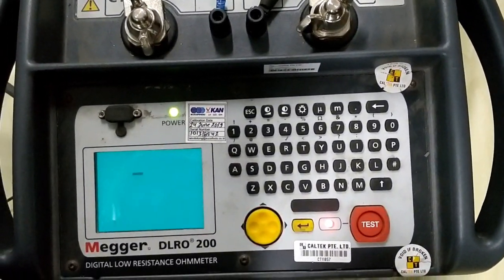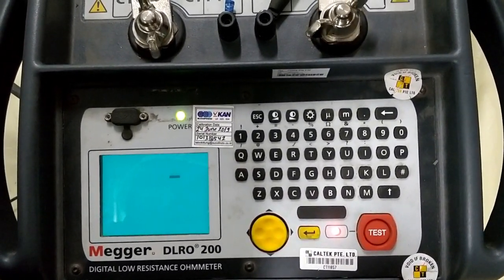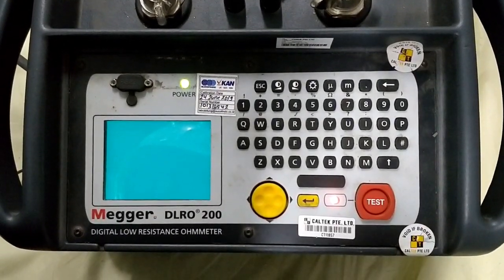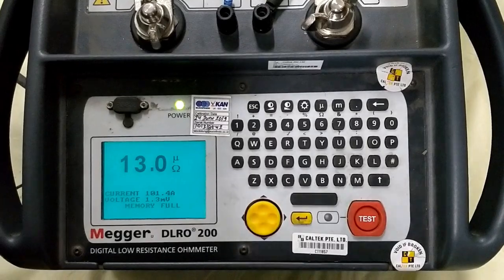Now I have injected the current and the kit is calculating the contact resistance. For Y phase we got 13 micro ohm.